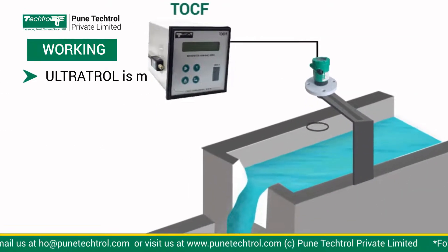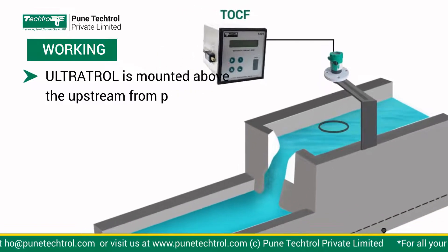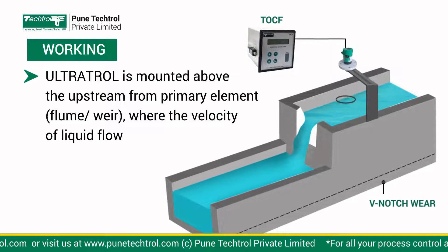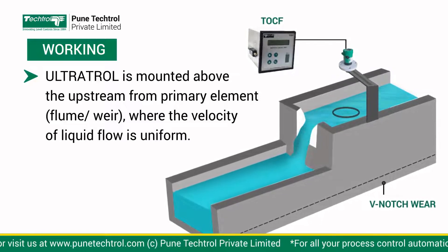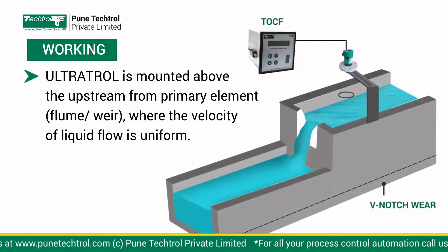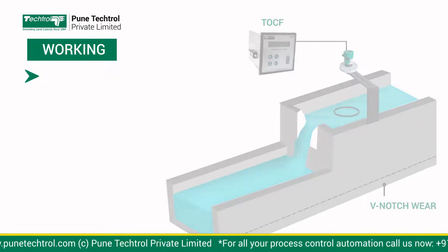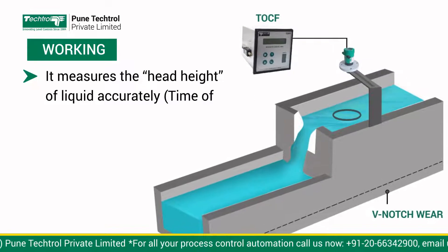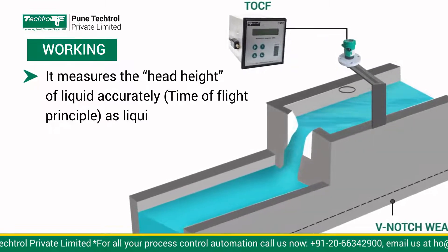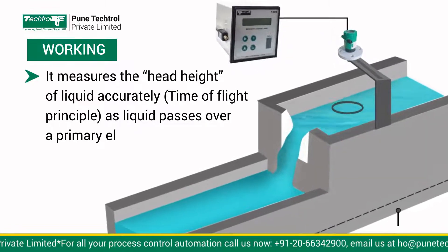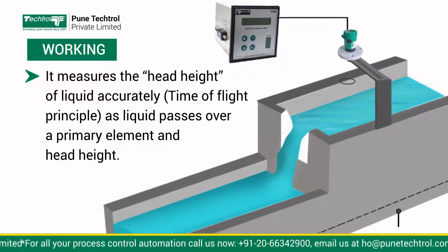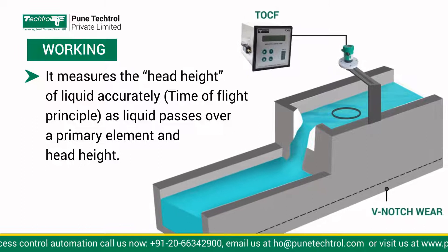Ultratrol is mounted above and upstream from the primary element where the velocity of liquid flow is uniform. It measures the head height of liquid accurately as liquid passes over a primary element. The output of Ultratrol is connected to the flow meter, which has a built-in formula to calculate flow corresponding to the chosen primary element and head height.